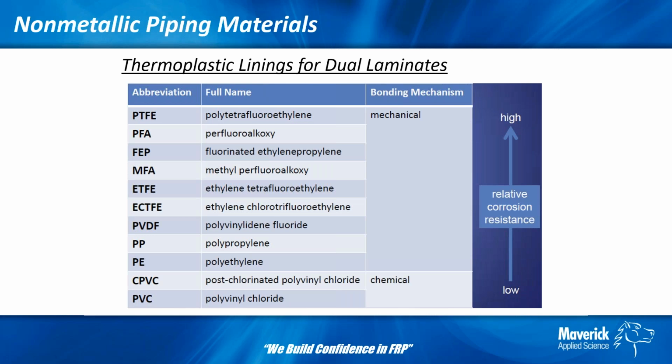Generally speaking, for rough ballparks, most of your linings are going to be around 3 to 4 millimeters, which is pretty typical. They could get a little bit thicker if you go to some heavy wall CPVC or something like that, but that's pretty typical of thicknesses.